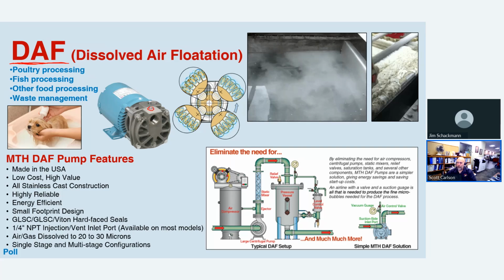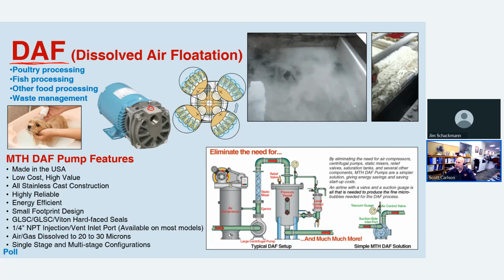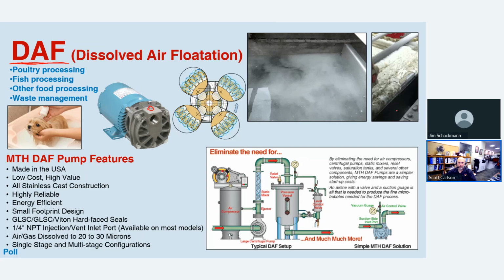directly into the suction side of the pump, and the air will pull itself in on a vacuum and will mix inside of the impeller and water channel, and it'll shear the bubbles to make these micro bubbles, which kind of looks like smoke in clear water, and they grab onto the particles and pull them up to the surface where they can be skimmed off so that you can either dispose of the water properly or reuse it in a different process inside of whatever facility is using it.